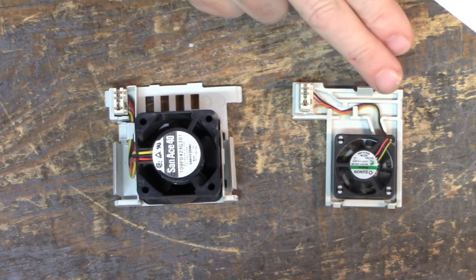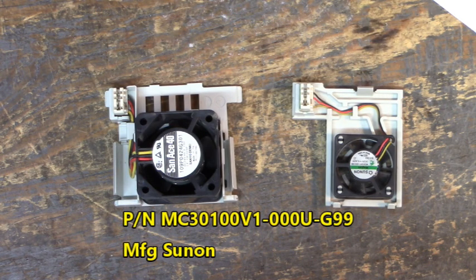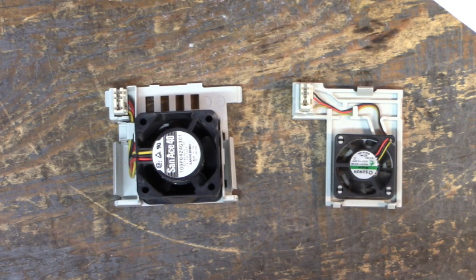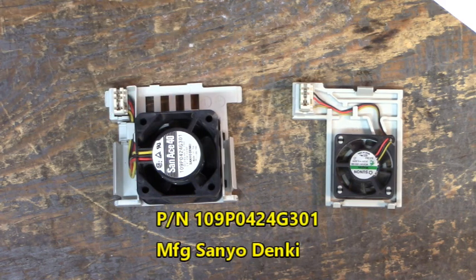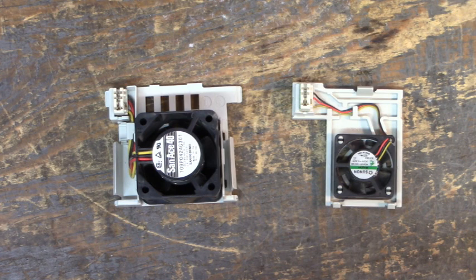Now the part number of the smaller one is MC30100V1-000U-G99, manufactured by Sunon. And this larger one is manufactured by Sanyo Denki, and it is part number 109P0424G301. The complaint with the Lenze drive is that it would fault on bad fan, cooling fan not working.